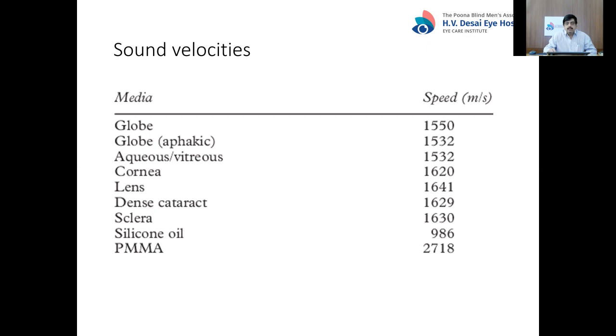The cornea has a speed of 1620 meters per second, but being very thin at only 500 microns, it is not taken into consideration during calculation. The lens has a speed of 1641 meters per second; however, depending on the grade of cataract, this may differ — a dense cataract may have a slightly slower speed of 1629. The sclera is around 1630 meters per second. Silicone oil slows sound to 986–1040 meters per second, and IOL materials like PMMA have a speed of 2718 meters per second.